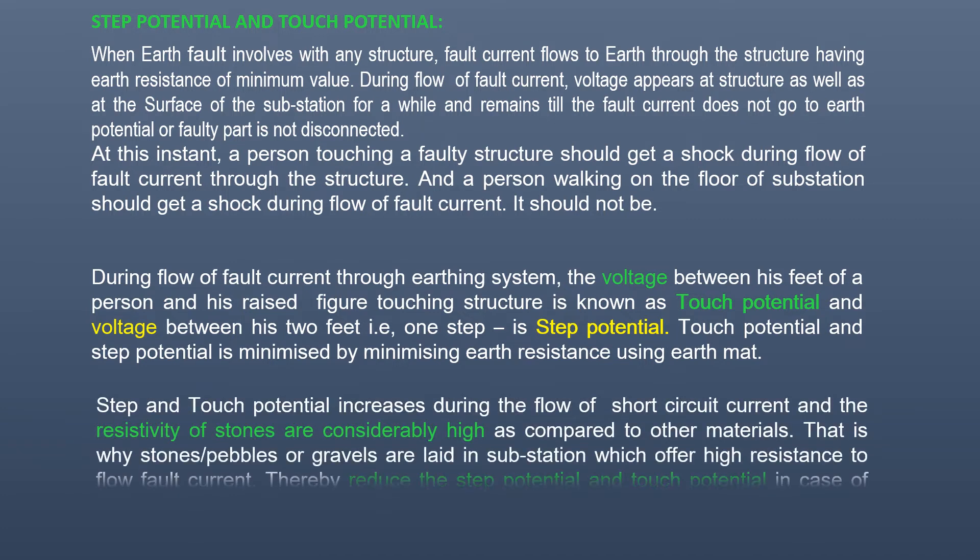Step and touch potential increases during the flow of short circuit current, and the resistivity of stones are considerably high as compared to other materials. That is why stones or pebbles or gravels are laid in the substation which offer high resistance to flow of fault current, thereby reduces the step potential and touch potential in case of maintenance or working on live equipment.